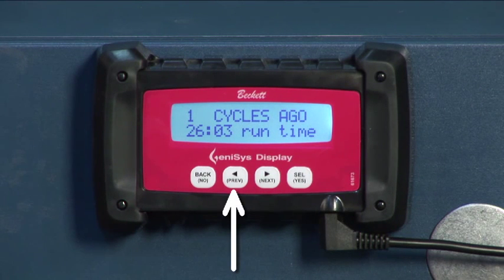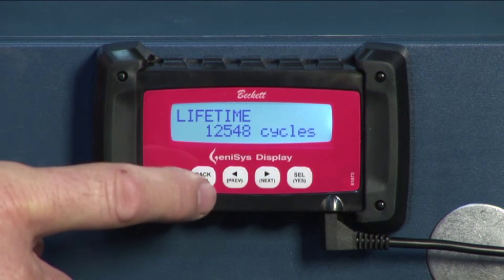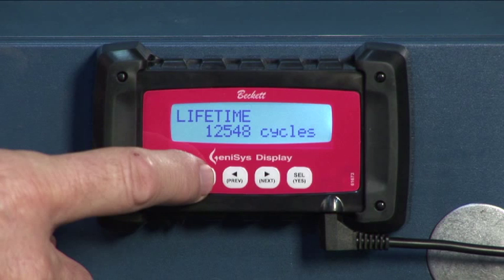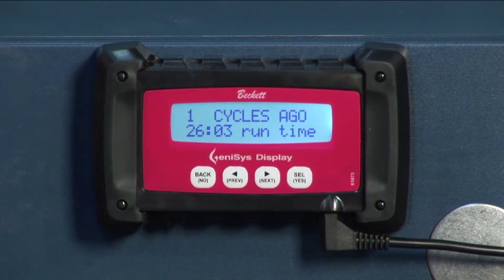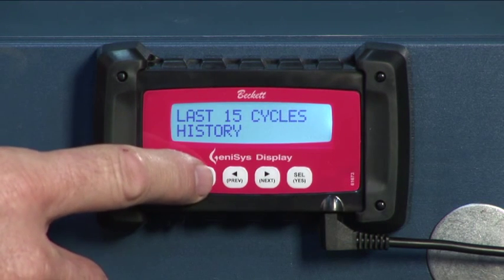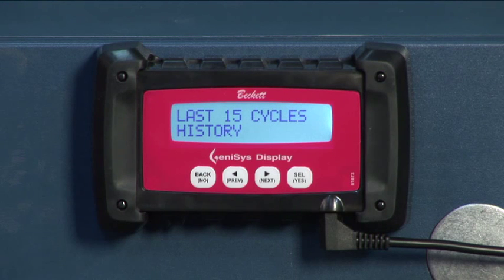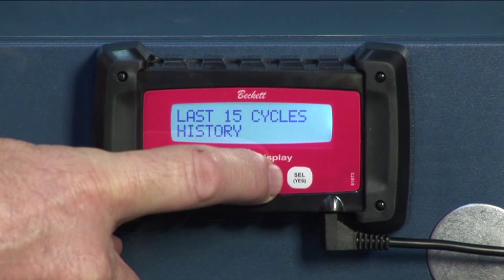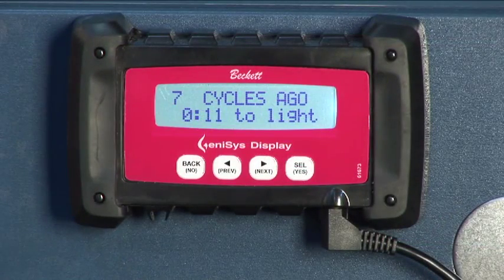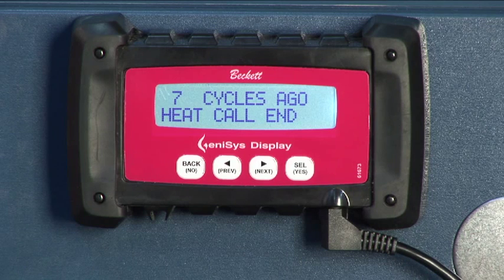Hit PREV if you need to return to burner status, or press SEL to display the last 15 cycles history screen. Note: if you want to view the lifetime cycles from the screen, press the next key to display the cycles. Press SEL yes to display the single parameter's readings through the 15 burner cycles. For example, use SEL yes and back no to scroll through the run time for all 15 cycles. To view another parameter besides run time, press the next or PREV keys. We can view the time required to light the burner in seconds, the CAD cell maximum, average resistance, the average voltage, the cycle end reason, and the time the burner remained off.